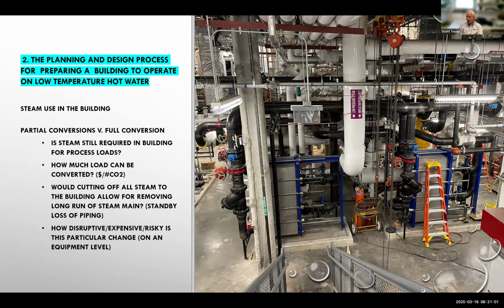The coil sized for lower temperature but running on higher temperature temporarily may need a control valve change, but it's just as likely that it will work in a different segment of the control valve's normal operating range. Or you may decide on a partial conversion because you don't have a solution to cutting off process steam, which is the case for us in some of the science buildings. In our biology buildings, we did partial conversions because we still need steam for cage washing, autoclaves, and other processes.